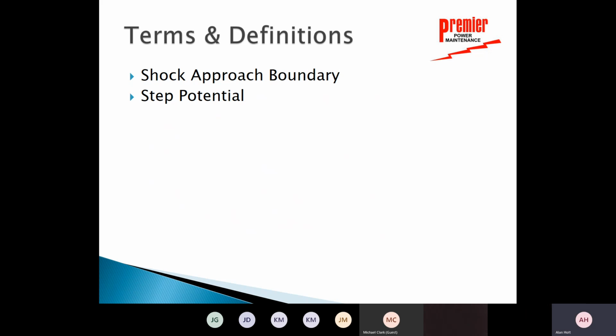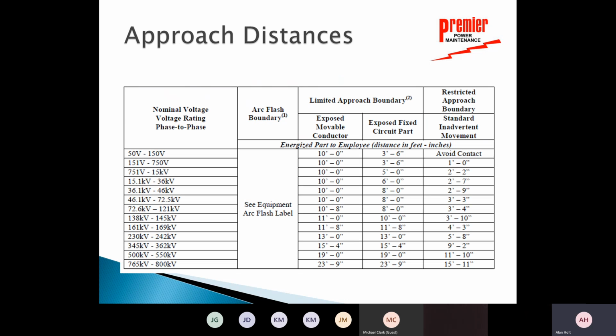So we talk a little bit about shock approach boundary. That's again the approach boundary for electrical shock. Step potential. We would want to make sure that we are working in an area with a ground grid. That greatly reduces the step potential. If you're working in an area that does not have a ground grid, this is just not likely inside Marathon property because they have enough hazards there that they're going to have a ground grid. But you have to be concerned about the step potential from one foot being in one place and another foot being in another place and a fault occurring.